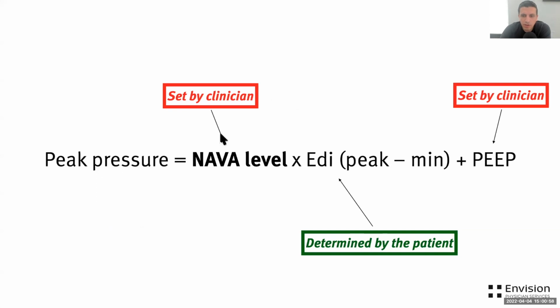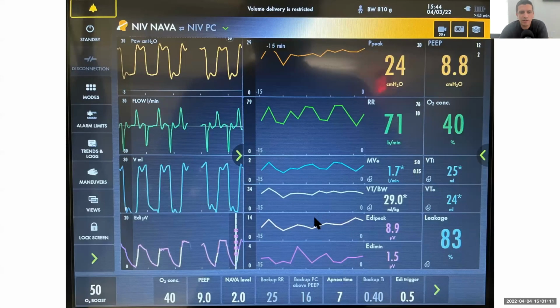So what's important to realize here is that the NAVA level you set on the vent, the PEEP is what you set, the EDI is something that is determined by the patient, okay? So this is a patient that we have in our unit right now. And this is sort of how the Servo U looks when you're putting up all the different graphs. So here at the bottom, you can see PEEP is 9, NAVA level is 2, and that's really it. That's all you need to know. That's all the settings we need.